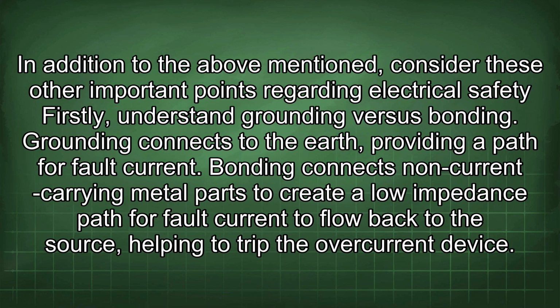In addition to the above, consider these other important points regarding electrical safety. Firstly, understand grounding versus bonding. Grounding connects to the earth, providing a path for fault current. Bonding connects non-current carrying metal parts to create a low impedance path for fault current to flow back to the source, helping to trip the overcurrent device.